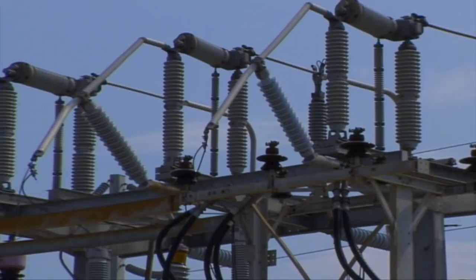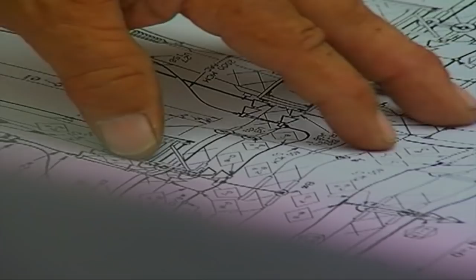Voltages over 50 kilovolts require distances greater than 10 feet. Scaffolds can only be closer to overhead power lines if such proximity is necessary for the type of work being performed and if the power company or electrical system operator has been notified and has either de-energized the lines, relocated the lines, or installed protective coverings over the lines to prevent accidental contact with the lines.